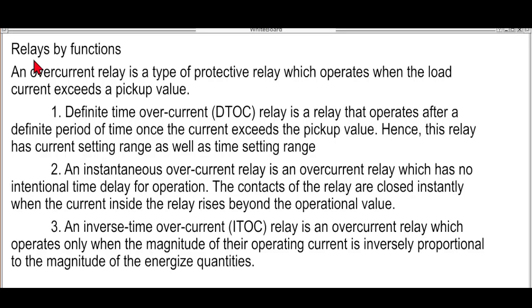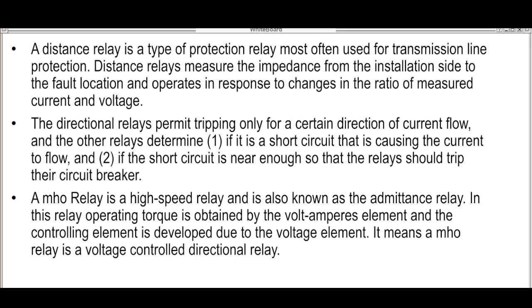So we have relays by function. The overcurrent relay will detect overcurrent, which exceeds the load value. For definite time overcurrent, the relay will operate after the current exceeds the pickup value. The instantaneous one trips automatically. Inverse time depends on the magnitude of the overcurrent: the larger the overcurrent value, the faster the inverse time overcurrent relay trips.